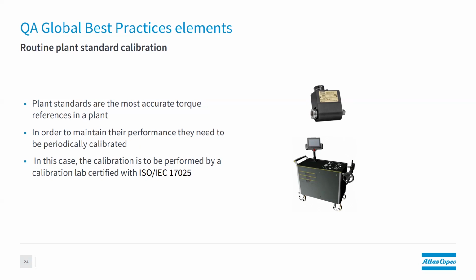Of course, you cannot calibrate them with the same types of transducers - you need transducers that are even more accurate. For this reason, this type of calibration is usually performed by a calibration lab, and the calibration should be certified with an ISO 17025 certification. This is needed to ensure your plant standards are still working correctly.